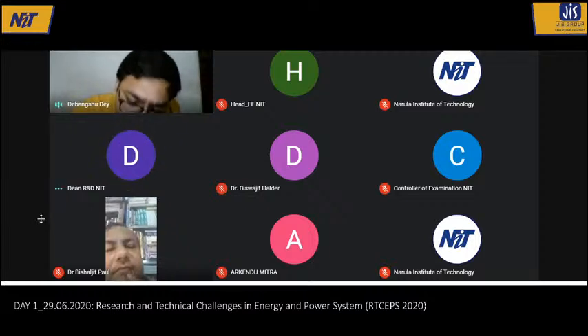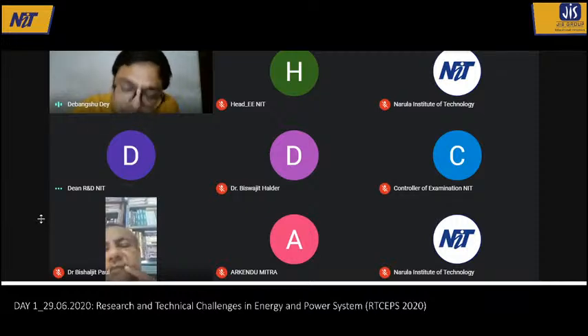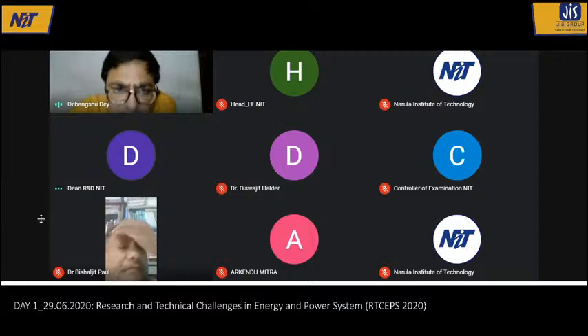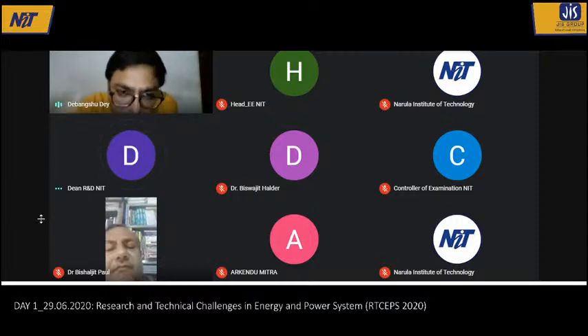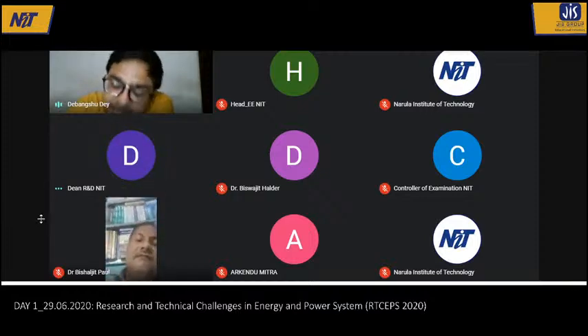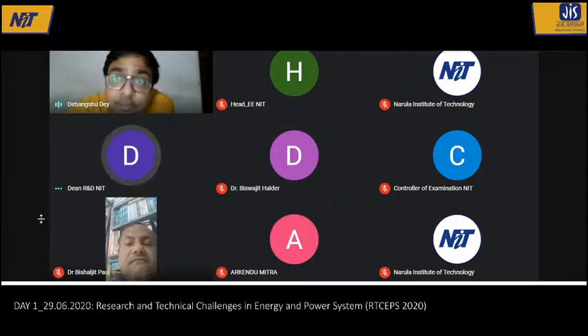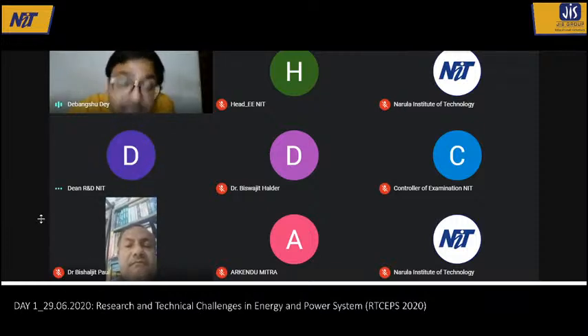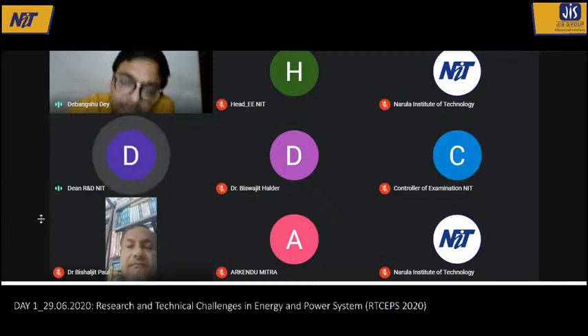For rated transformers, the impulse voltage standard is given based on rating, for example a 3 MVA transformer at 33 kV. Now, if for that same transformer we are trying to understand the condition of the overall insulation, not the impulse withstand, then we should go for the step test. Again, the rating will depend.